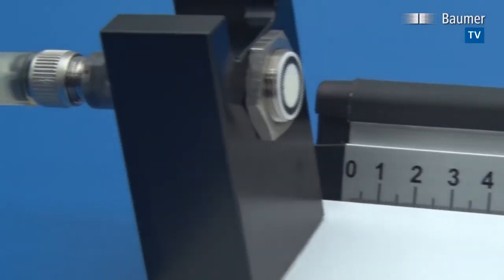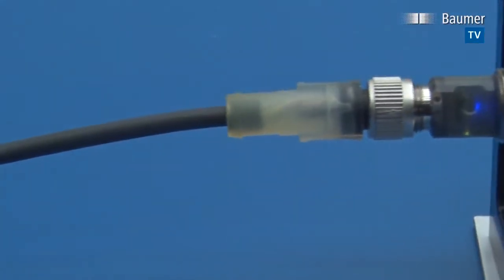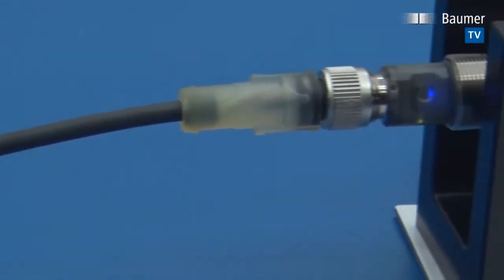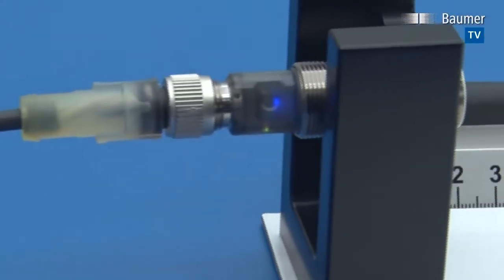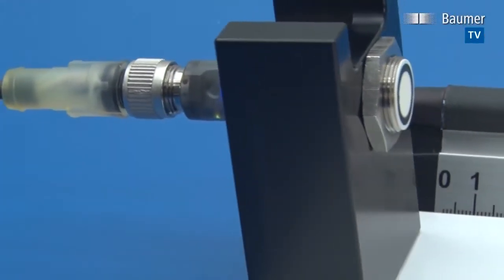This sensor has three levels to teach. Level one is a one-point teach, and the position of reflector might change by plus-minus five percent. Level two is also a one-point teach, and the position of reflector might change by plus-minus ten percent. Level three is a factory reset.